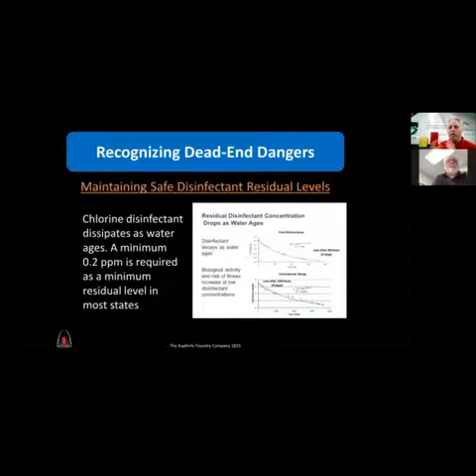After about a week, it drops off very quickly. The dissipation rate is about 1.5 ppm per week after that initial week. If you're using a combined chlorine or chloramines, which larger cities or larger rural water districts use, it's about half that rate — it stays in the water about twice as long, a couple of weeks. After that, the dissipation rate is about 0.625 ppm per week.